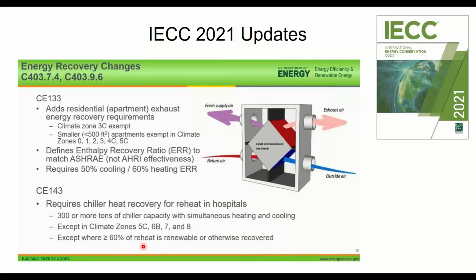This one will affect you. Right now, ERVs are required for lots of project types whenever you have a certain amount of outside air, which isn't very much anymore these days, so you have to do these ERVs. One of the main exceptions to not doing the ERV today is if you have multiple exhaust fans for the building—you could say you've got all these little exhaust fans from each apartment, so you don't have to do the ERV per that exception. That exception is going away and will no longer be available.